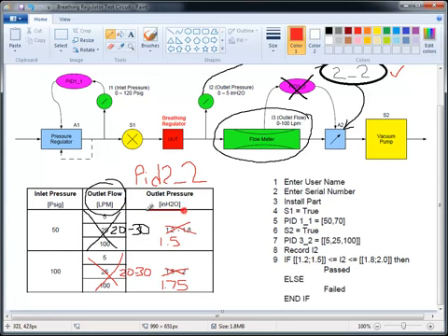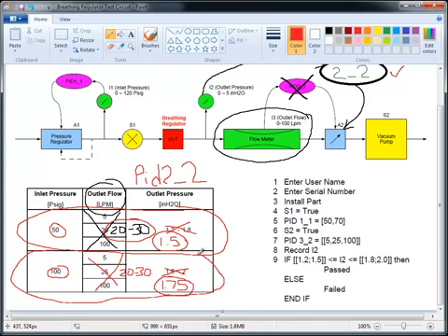So again, we're going to set an inlet pressure of 50 psig and an outlet pressure of 1.5, and then measure the resulting flow, and it must be within a range between 20 and 30. And then we're going to do it again for 100 and 1.75 on the outlet pressure, and it must attain the same flow range right here in order for the test to pass.